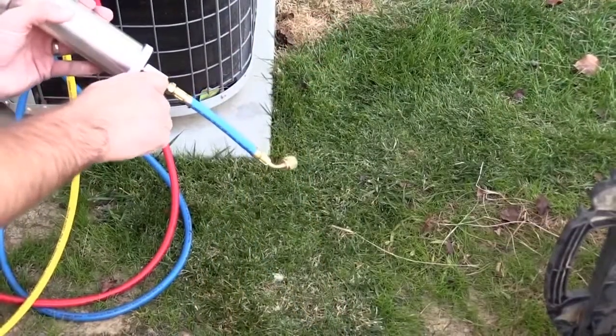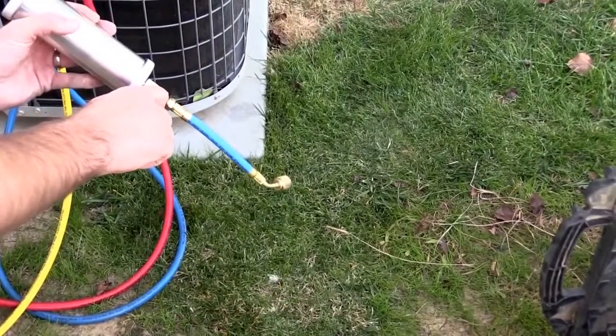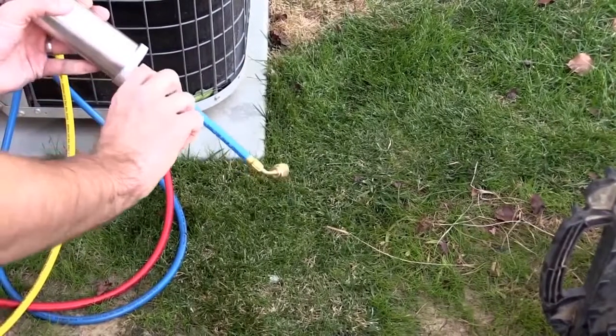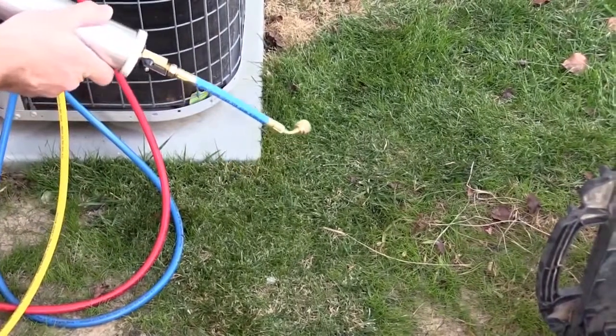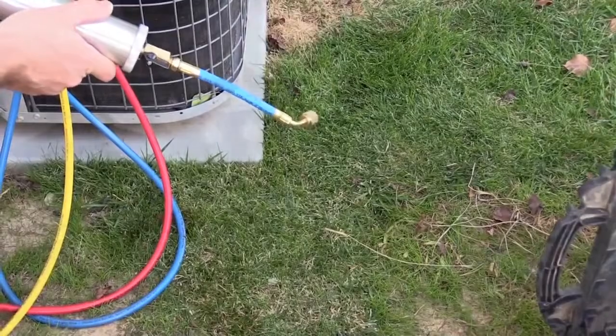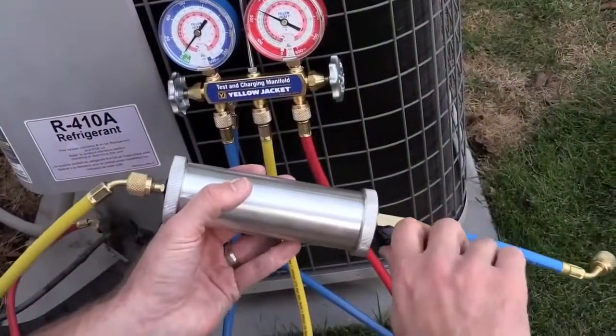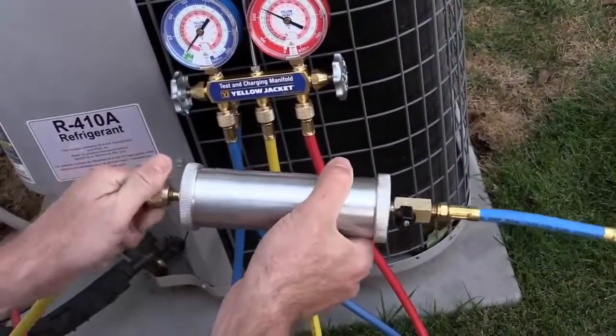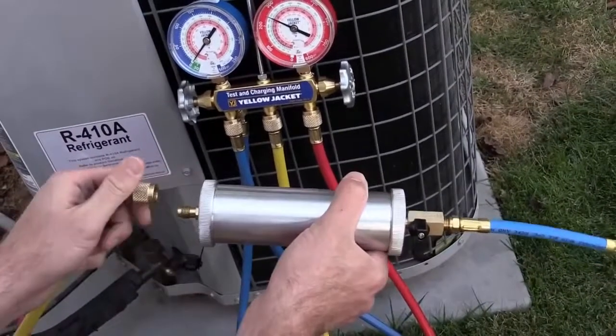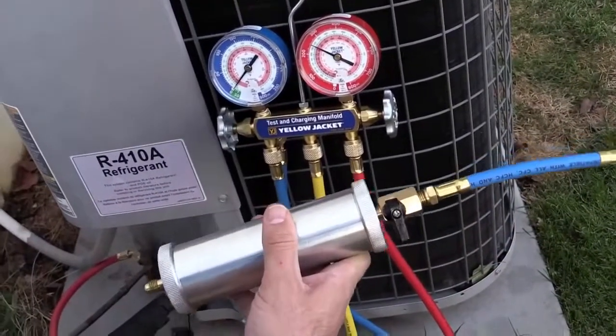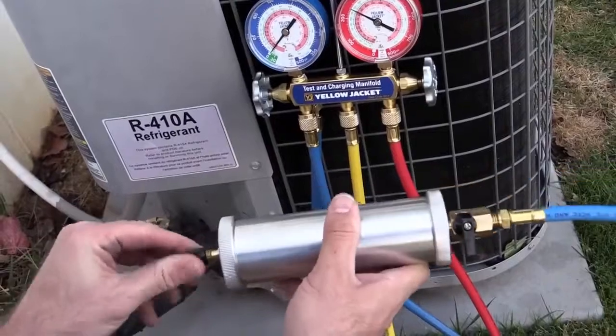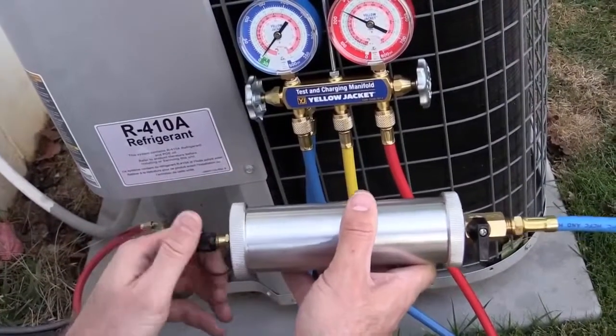Once disconnected, slowly open the hand valve so it equalizes the assembly to atmospheric pressure. Ensure the outlet fitting is pointed toward the ground, directing any discharge away from the body. Once fully discharged, close the hand valve and remove the yellow manifold hose from the injector. Return the cap to the Schrader fitting to prevent contamination before the tool's next use.